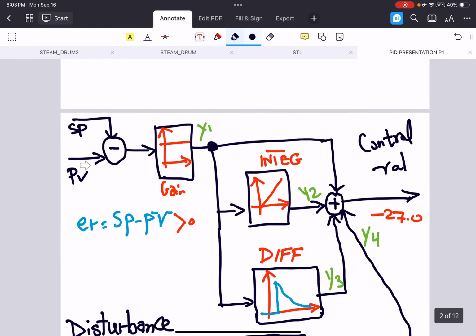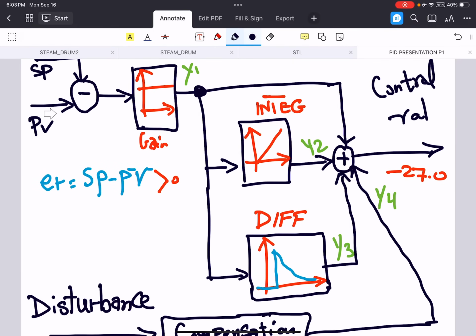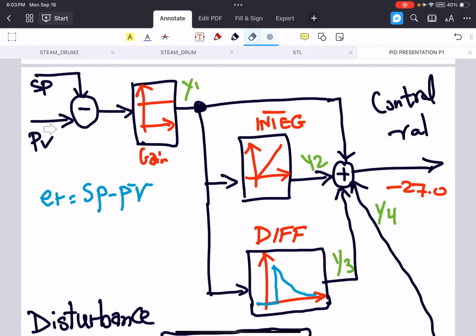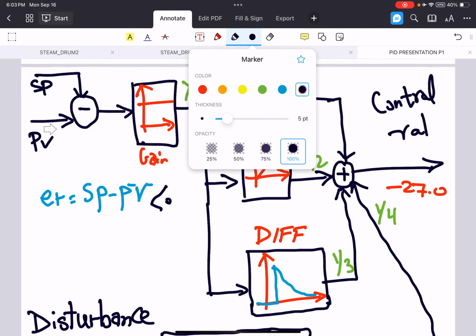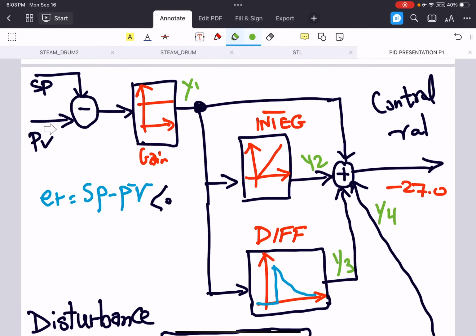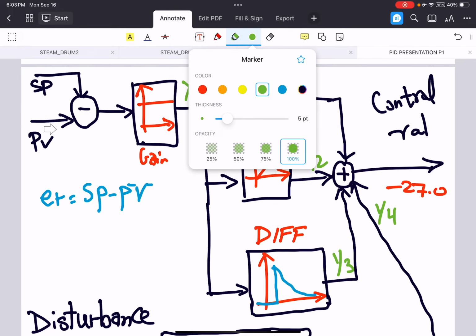So let us just refer to the PID algorithm here. You can see that in the PID algorithm, in this specific case, the error, set value minus process value, is less than 0. For error less than 0, it's a negative value. And in this case, for Siemens technology, it's advised to use a negative gain.